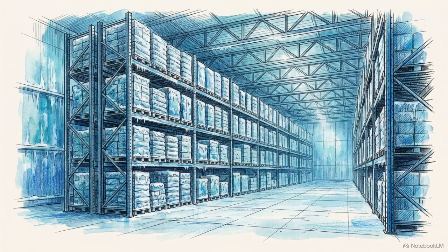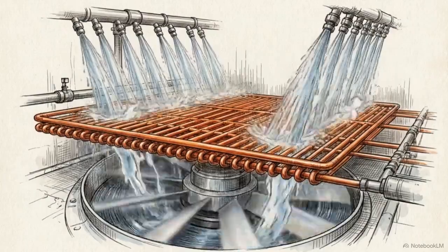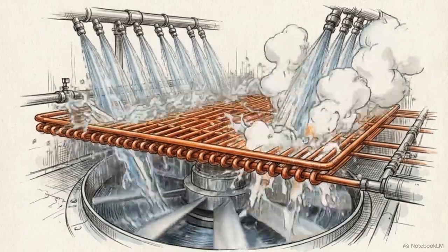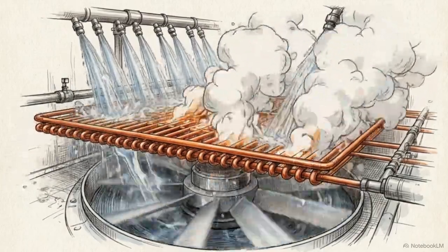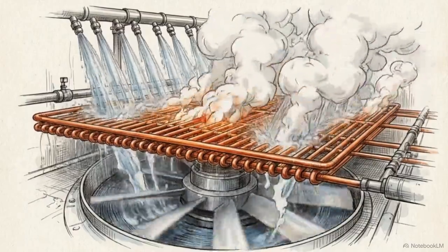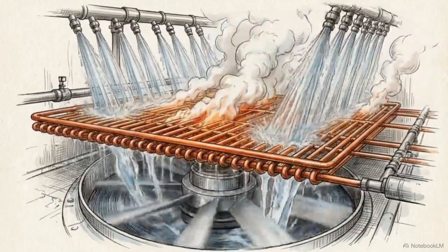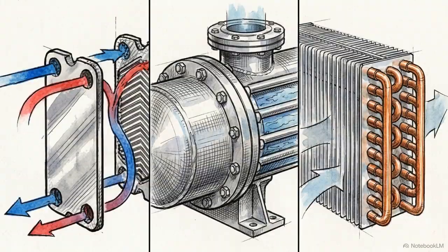For environments like large-scale cold storage and industrial refrigeration, evaporative condensers provide a highly efficient hybrid solution. By spraying water directly over the hot coils while forcing ambient air across them, the system utilizes the massive energy required for rapid evaporation, stripping heat away from the coils instantly. Whether it is a dense plate exchanger, a water shell, or a traditional air coil, the architectural design is dictated strictly by the required thermal load and the physical properties of the chosen cooling medium.